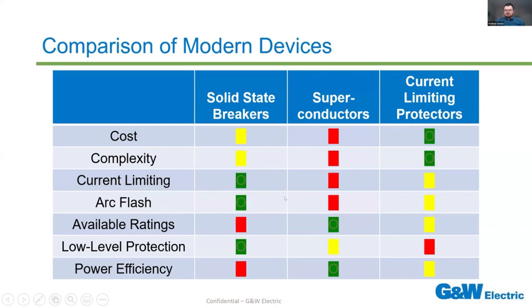Once again, there are limitations to those breakers, though, that went before. And in second place, current limiting protectors will definitely be there. Once again, it limits that fault in 1/4 to 1/2 an electrical cycle. It's going to completely clear that fault or arc flash event, depending on the scenario. Superconductors come in last just because you would have to run a long length of cable. There's no guarantee just because you increase the resistance that the arc flash or current or fault current event is going to end.